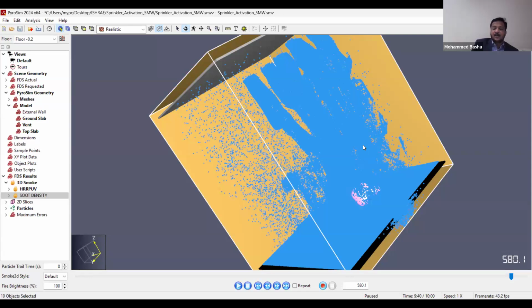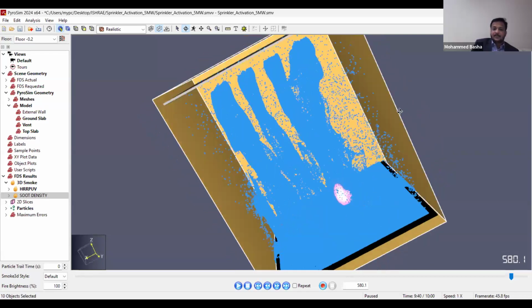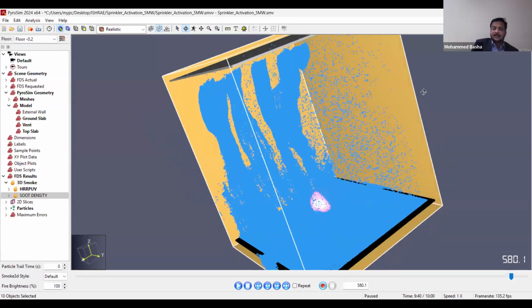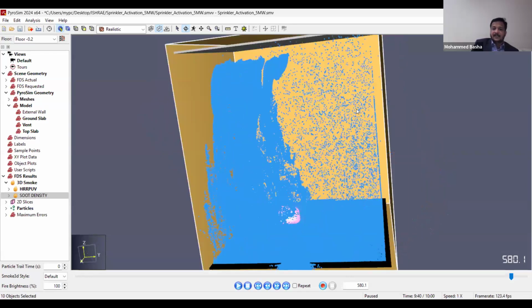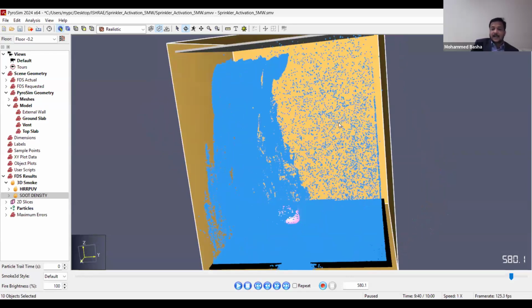the concept. Then we do not need to have a smoke control system, right? When the occupants can evacuate, then why do we need to have a smoke control system? It is to maintain the tenability all the time during the evacuation. So you now understand the importance of doing the Alpert's equation along with the CFD analysis to see what's happening in a real picture. This is mostly important if you don't know the Q value. Now let's go back to our slides and we'll finish the remaining areas.